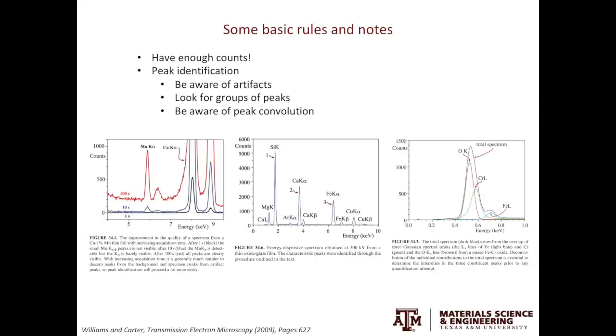Whenever doing EDS, you need to have a few things in mind. The first is, you need to ensure you have enough counts. You have seen a similar example before, when the acquisition time is too short, you don't see the manganese K-alpha peak. As you increase the acquisition time, the manganese K-alpha peak becomes more prominent.